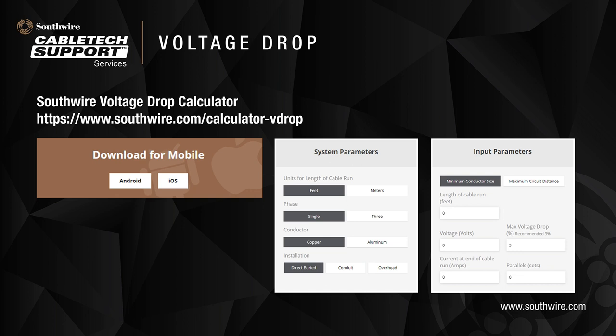The basic input parameters for the calculations are minimum conductor size or maximum circuit distance, the voltage of the system, the maximum allowed voltage drop, and the current in the circuit or system.